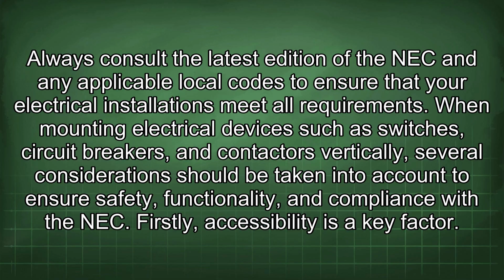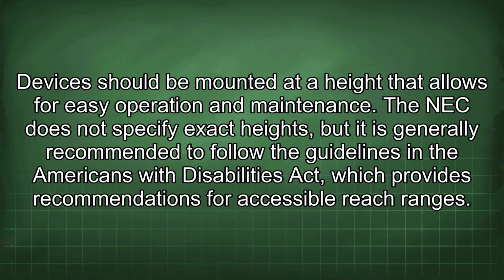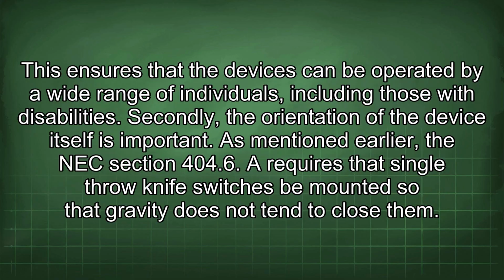Firstly, accessibility is a key factor. Devices should be mounted at a height that allows for easy operation and maintenance. The NEC does not specify exact heights, but it is generally recommended to follow the guidelines in the Americans with Disabilities Act, which provides recommendations for accessible reach ranges. This ensures that the devices can be operated by a wide range of individuals, including those with disabilities. Secondly, the orientation of the device itself is important.